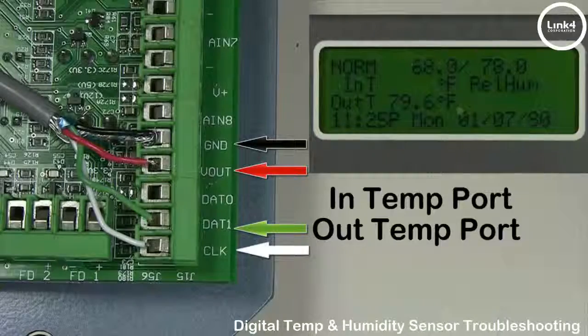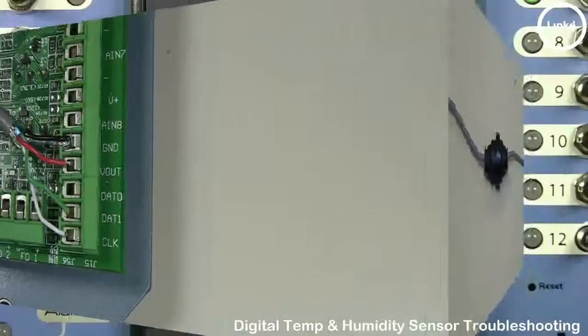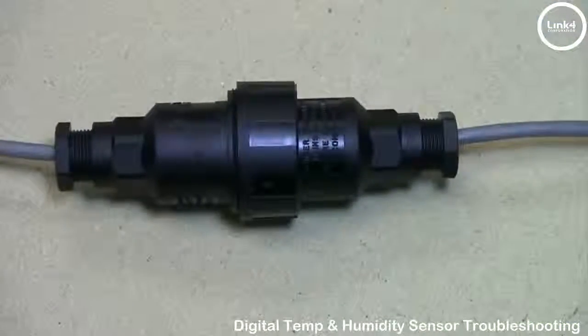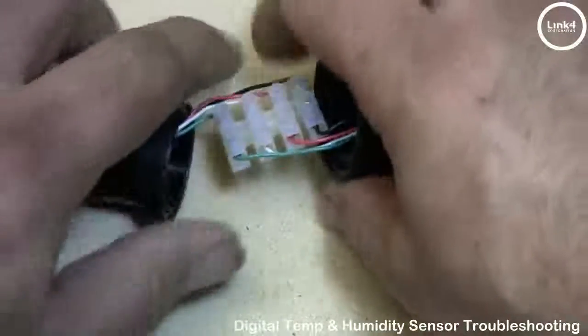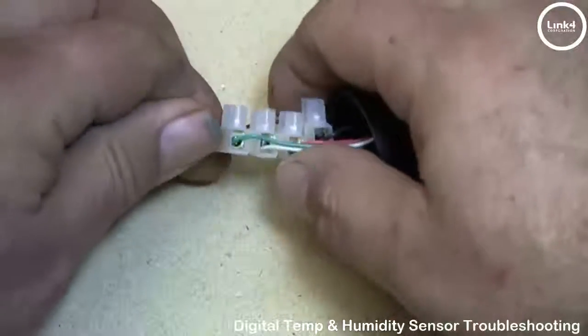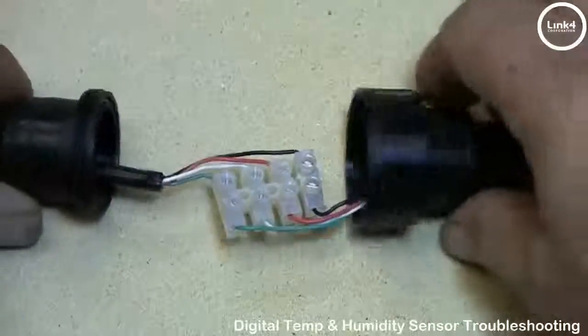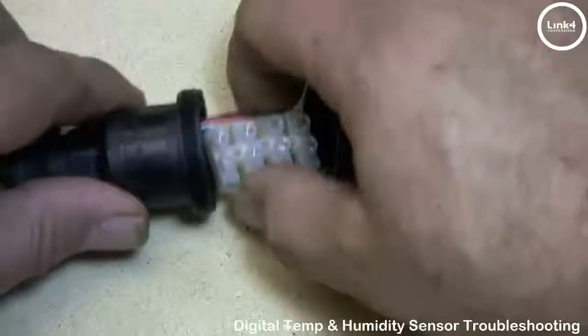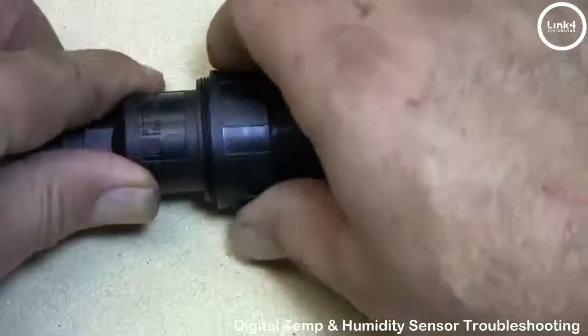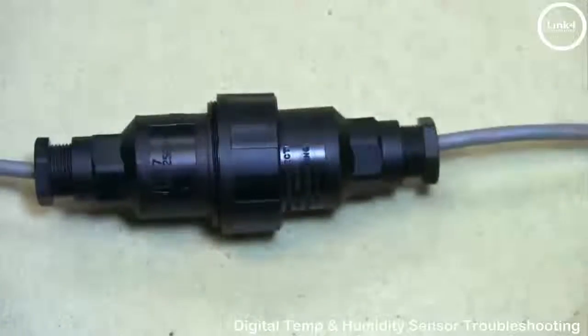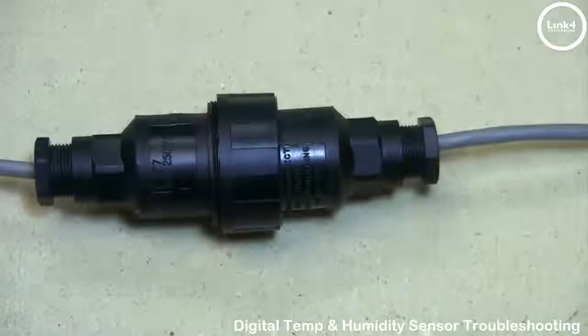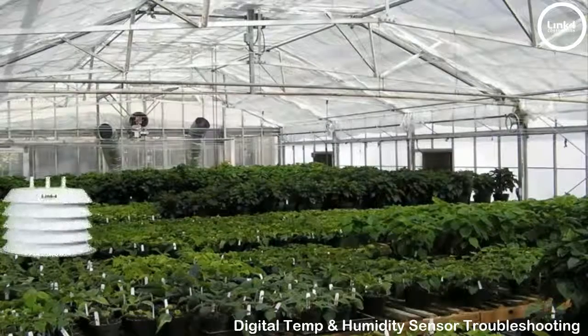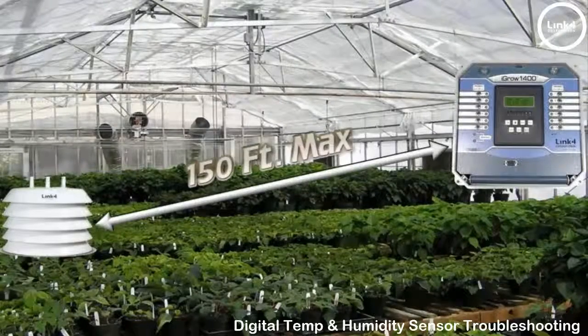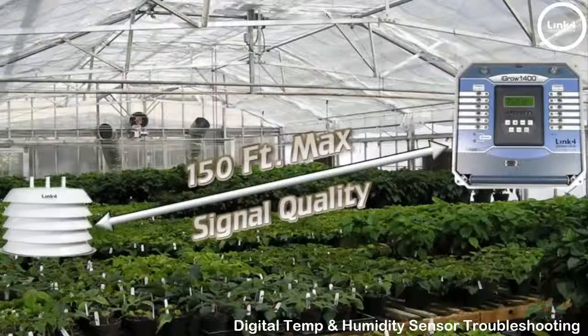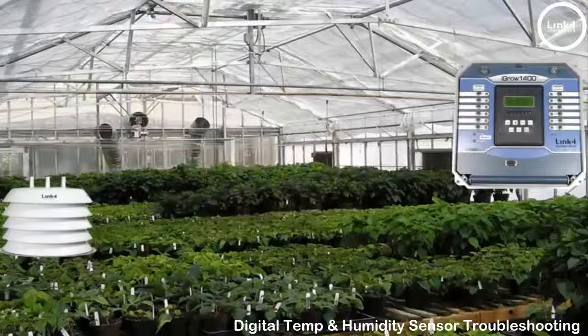If your sensor reading's still not populated, you may want to check if in fact you extended your sensor wiring, the junction box between the extension. You want to open the junction box up if present and see if there's any corrosion, moisture, or contamination, and if it's present, remove it. Also, inspect the sensor line for cuts or damage which will in fact affect your readings. Your sensor distance from the controller is important as well. The max distance is 150 feet for effective sensor readings.